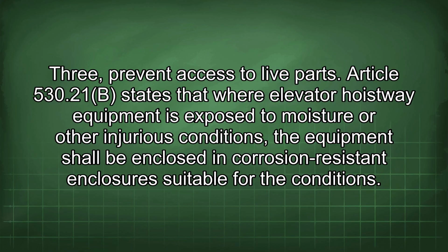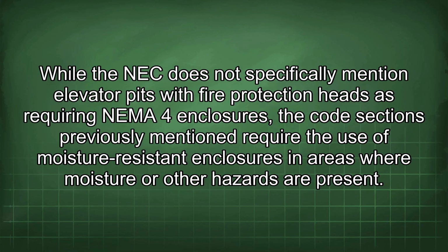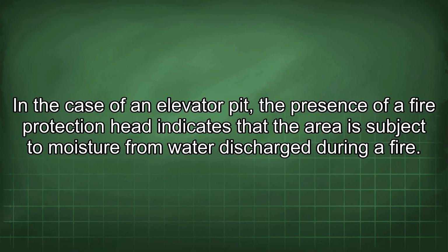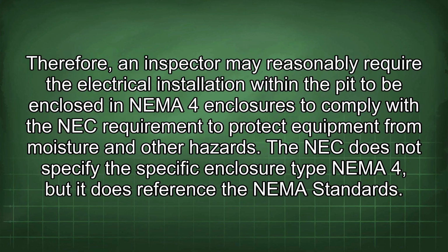Article 530.21b states that where elevator hoistway equipment is exposed to moisture or other injurious conditions, the equipment shall be enclosed in corrosion-resistant enclosures suitable for the conditions. While the NEC does not specifically mention elevator pits with fire protection heads as requiring NEMA 4 enclosures, the code sections previously mentioned require the use of moisture-resistant enclosures in areas where moisture or other hazards are present. In the case of an elevator pit, the presence of a fire protection head indicates that the area is subject to moisture from water discharged during a fire. Therefore, an inspector may reasonably require the electrical installation within the pit to be enclosed in NEMA 4 enclosures to comply with the NEC requirement to protect equipment from moisture and other hazards.